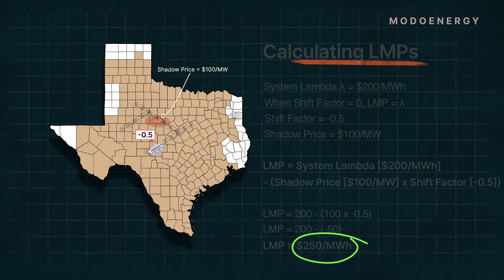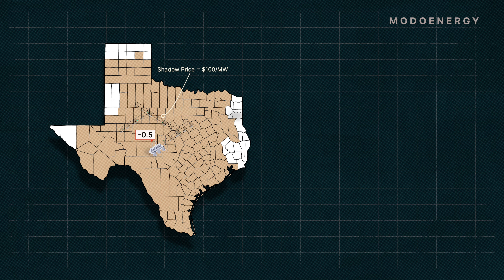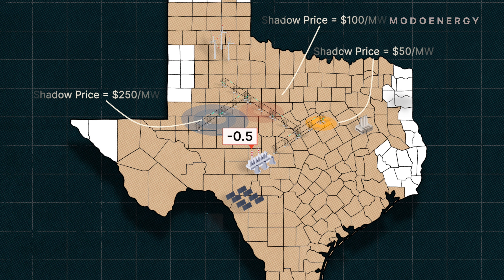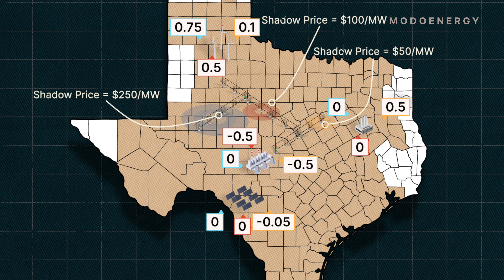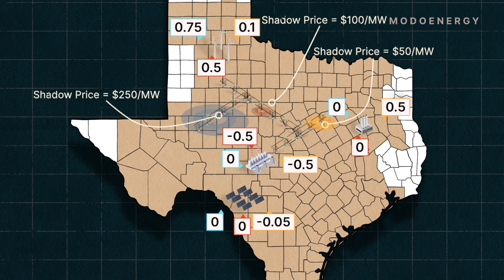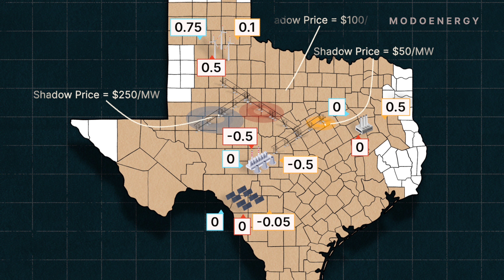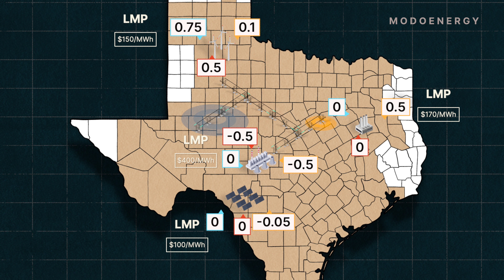When there are multiple constraints at the same time, ERCOT determines the LMPs by repeating the same calculation across every constraint and for every settlement point. It then finds the sum of all of these values at every settlement point, and then subtracts that value from the system lambda.